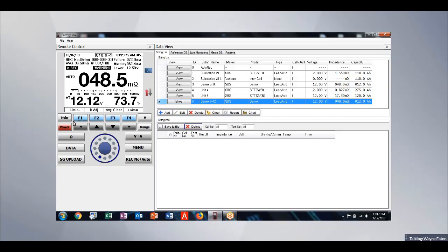You'll see that the warning goes from small case to uppercase, highlighted, and then back to small case. And that means that the reading has been stored and recorded. And then I can just move on to the next cell. So I can literally test these things at about 3 seconds per cell, or 3 seconds per battery, just long enough for the unit to stabilize and grab that reading.